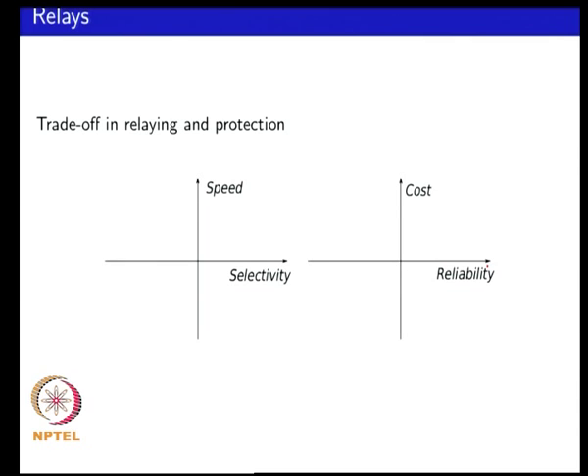When you want decisions at high speed you might be more prone to noise and making the wrong decision. So a trade-off might be that if your speed is very fast you might have poor selectivity, or if you are taking more time to make the right decision your speed is naturally less. Your ideal relay should be capable of operating at both high speed and high selectivity, but the trade-off within your algorithms would be between speed and selectivity.